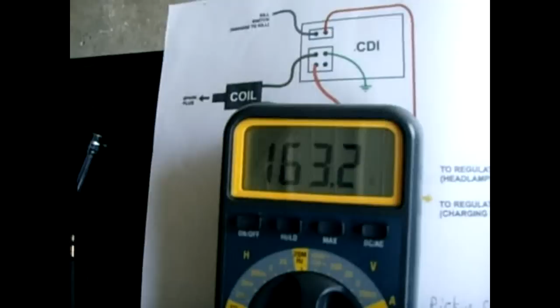To check that, set the meter to 200 ohms and leave it grounded. We get about 163 ohms. These can run between 140 and 185 or 190, so as long as you're in that range, you're good on that wire.